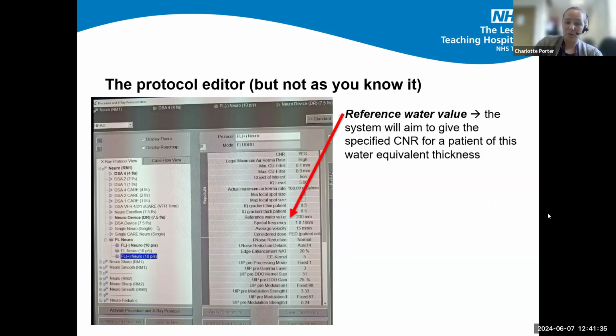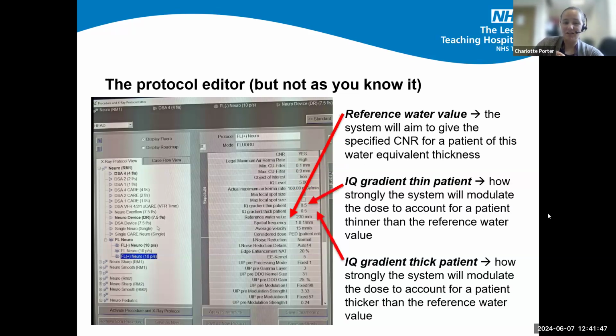This reference water value down here is the system aiming to give that CNR for a patient of that water equivalent thickness. So you may ask, how does it deal with thinner or thicker patients? And this value here is how it does that. It tells the system how to modulate to account for patients that are either thinner or thicker than that specific reference water value.